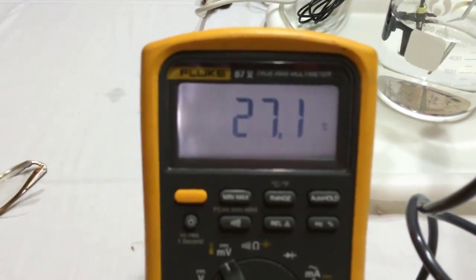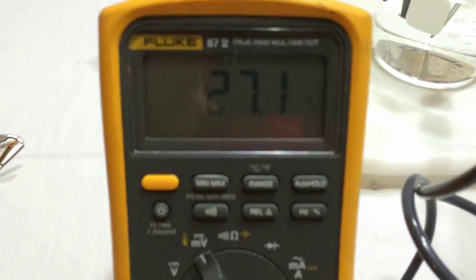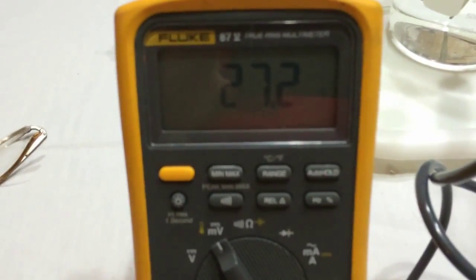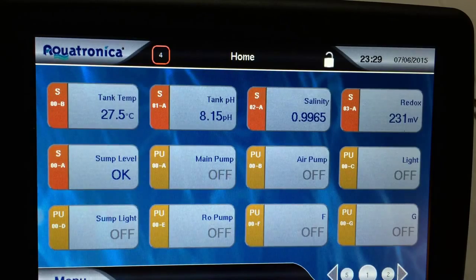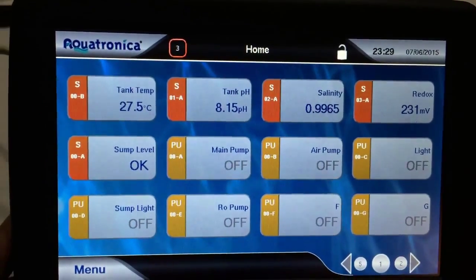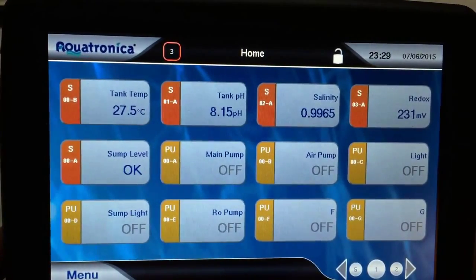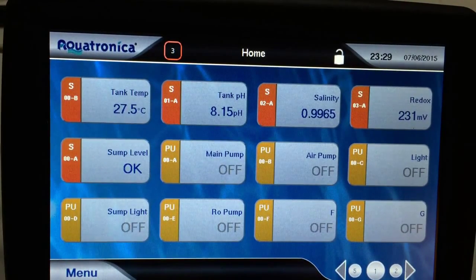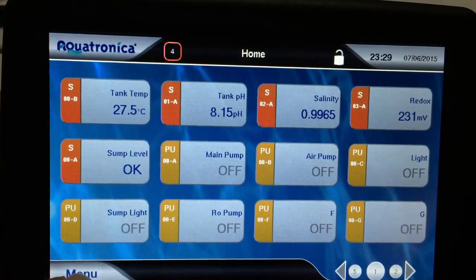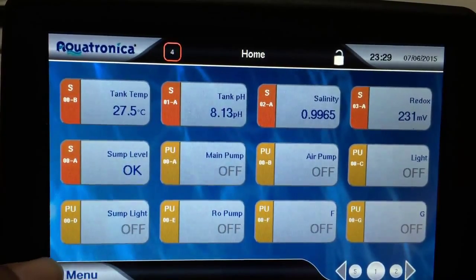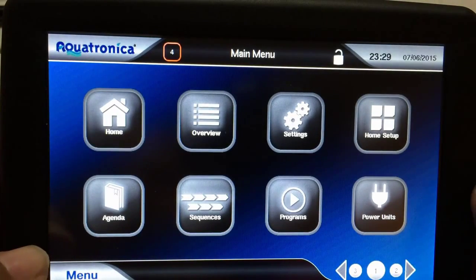As I said, here we're getting 27.1 degrees, and I'm going to turn off the backlight. 27.2, 27.1. Okay, well, what do you know? The Aquatronica is pretty accurate straight out of the box, as they claim. 27.5 degrees C, and I'm going to check over here. It's reading 27.2. So I'm still going to do a calibration, even though you really wouldn't need to, but I have it, so why not just do it and show the calibration in process.